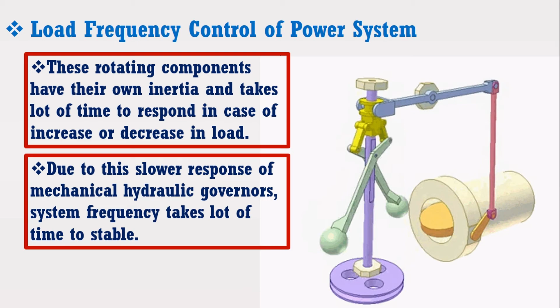In order to make the response faster, electro-hydraulic PID based governors or controllers are employed. Electro-hydraulic PID based governor or controller replaces the mechanical components of dashpot and piston with electrical components. As these electrical components are static in nature, they don't have inertia, due to which their response time is faster as compared to the mechanical hydraulic governor. Furthermore, PID controller provides robust, satisfactory control of frequency by changing the parameters of P, I and D gain.